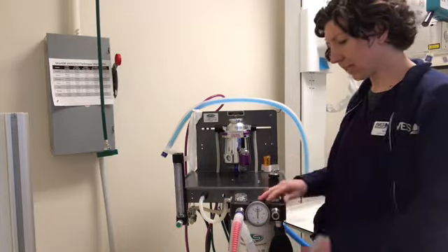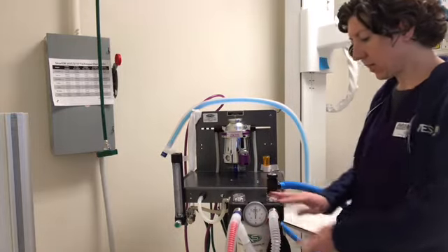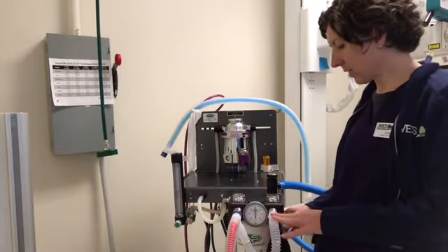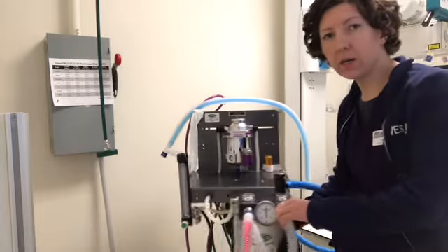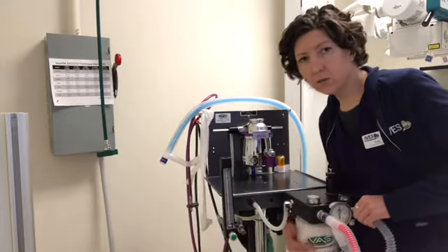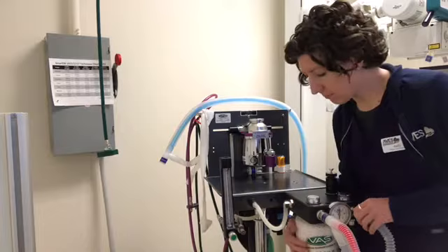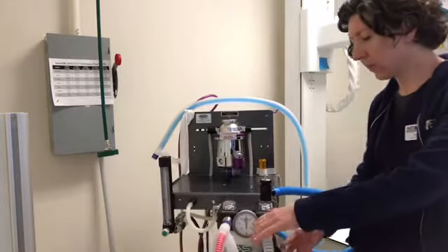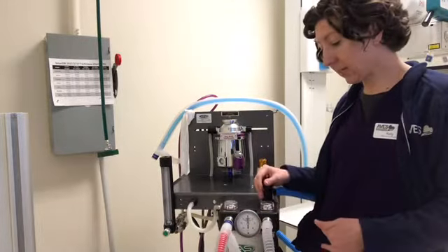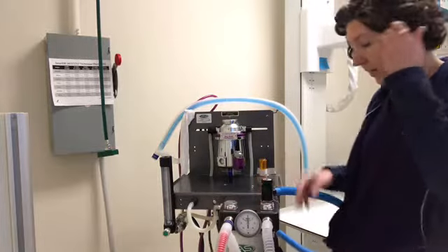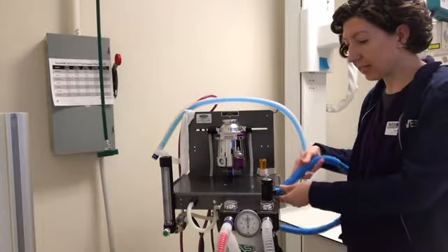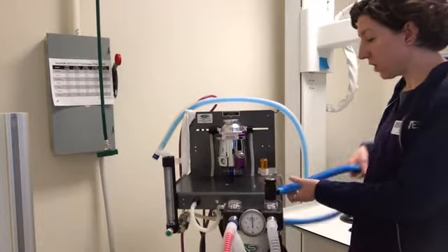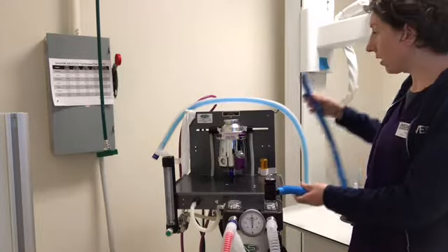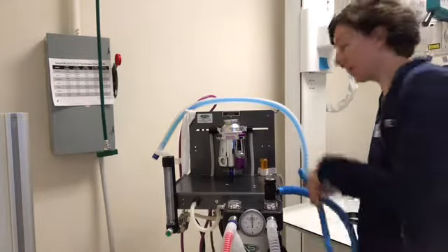When the patient exhales and the carrier gas and the anesthetic go through this soda lime canister, that's where it absorbs the excess carbon dioxide, and then it sends that gas here through the pop-off valve through the scavenging system tubing.